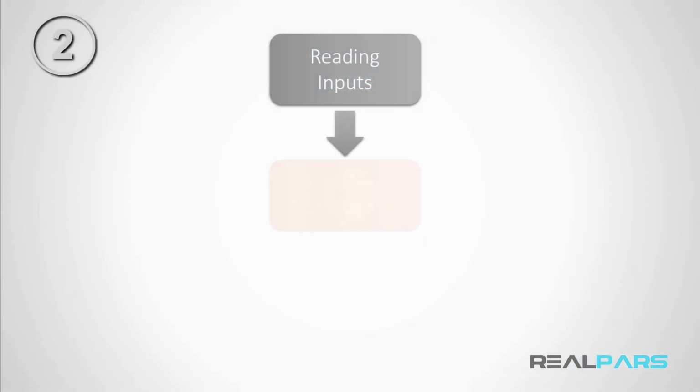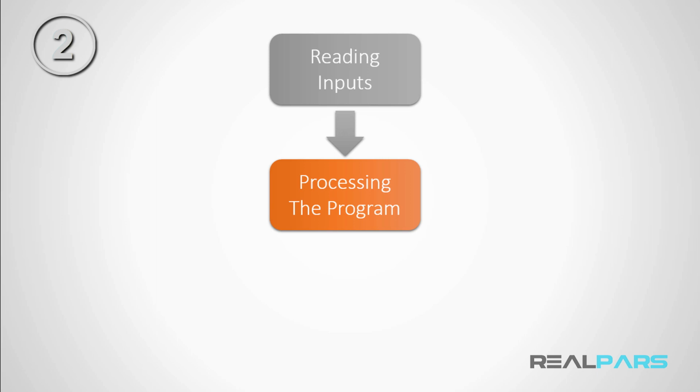In the second step, the CPU processes the program that we wrote in the OB1 and starts processing or solving the logic from the first network. As part of this process, when it sees an input address, it checks the status of the address in the PII and solves the logic based on that value. When it sees an output address, it saves the status to the PIQ.